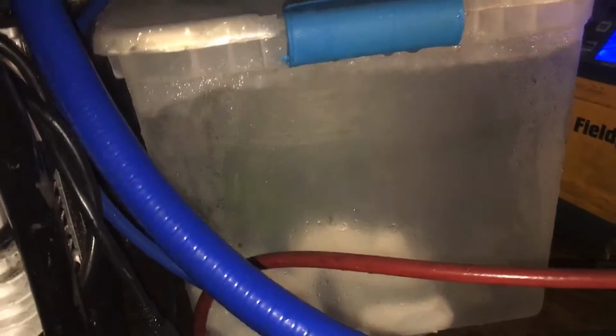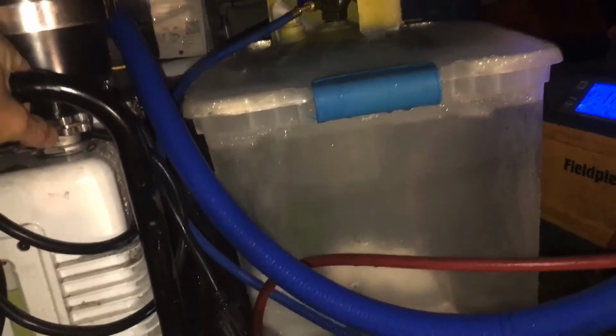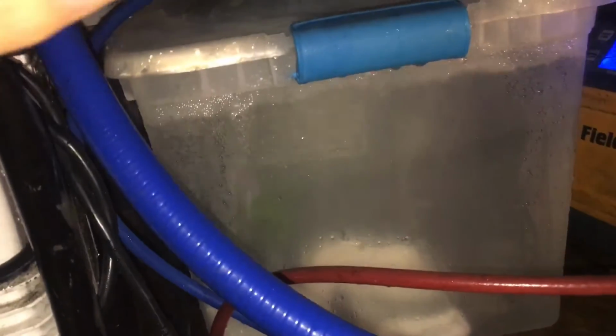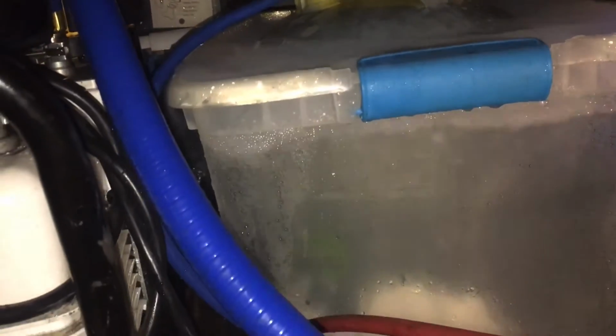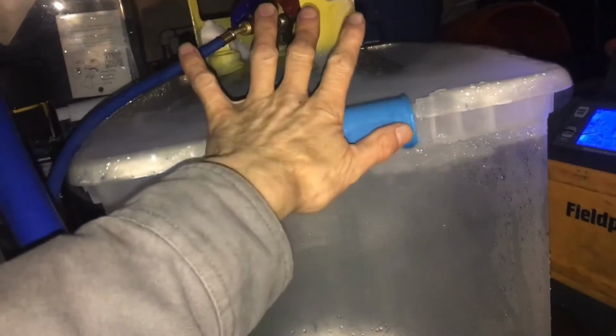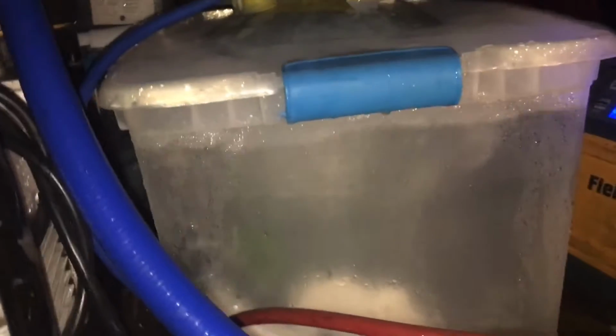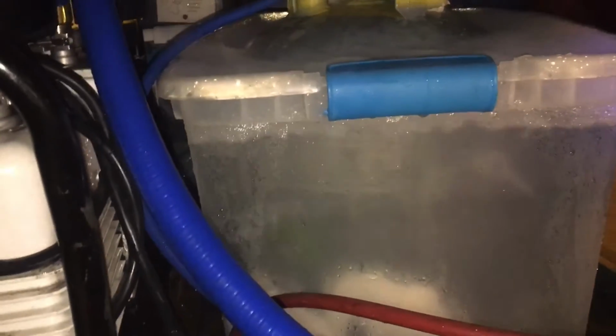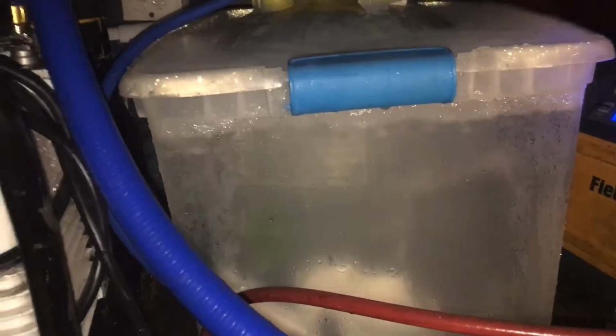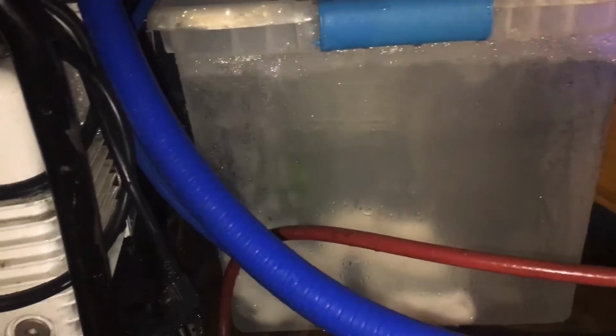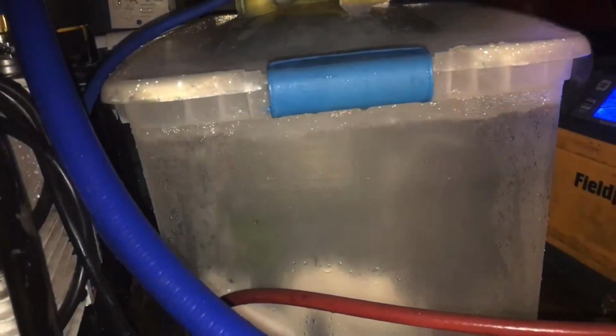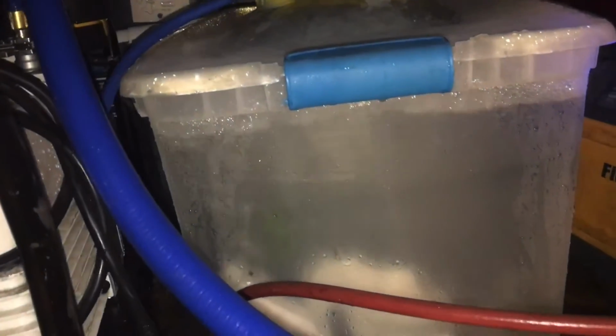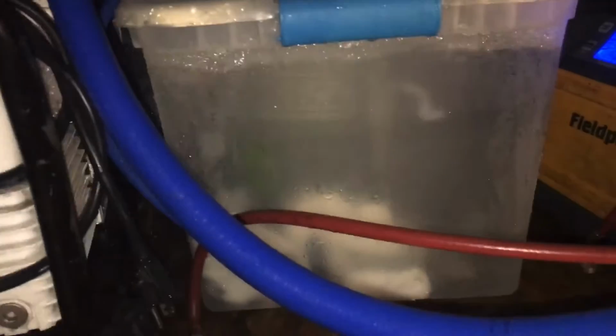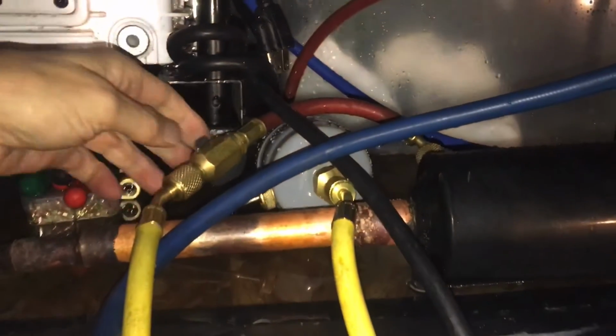So there's a problem. And oh, and another thing, since it's all new refrigerant in the system and it's never been opened, and I see the canisters upstairs, the other contractor, the other technician who came and dumped an extra 20 plus pounds in the system, he has 2 cans of fresh R410 upstairs on the roof right next to the units. So I'm not afraid of the refrigerant being contaminated. Some technicians will take old used crap out of other people's units, mix it all together and stick it into your systems and sell it to you all over again, and it's laden with moisture.